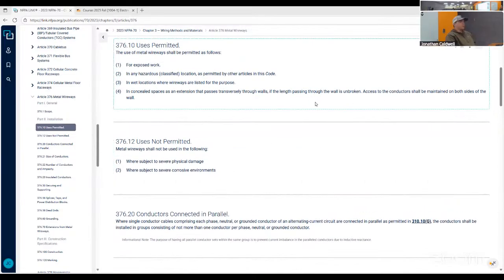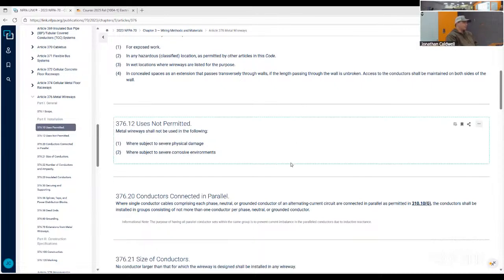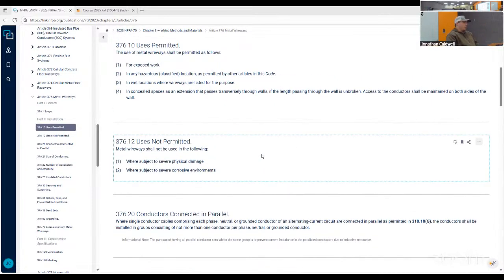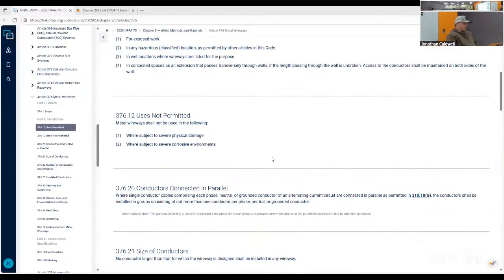And the reason it's important that you have access to both sides is that there is a cover on it. So you have to be able to access both sides. It can't just be buried behind a wall. Can't just run it inside a wall or whatever. Use is not permitted where subject to severe physical damage or severe corrosive environments. So severe physical damage would be like below 4 feet or whatever.